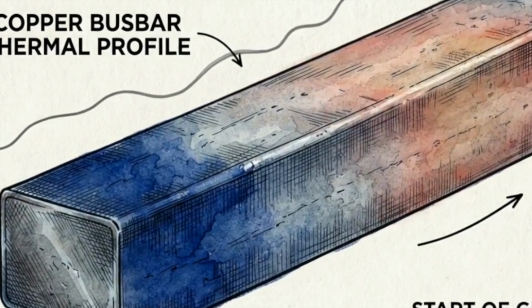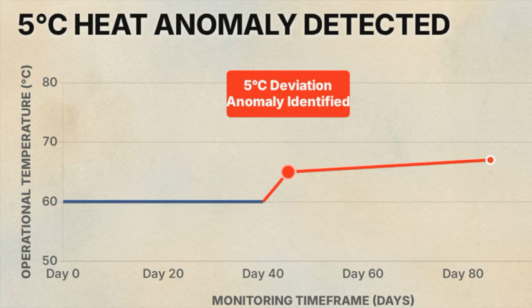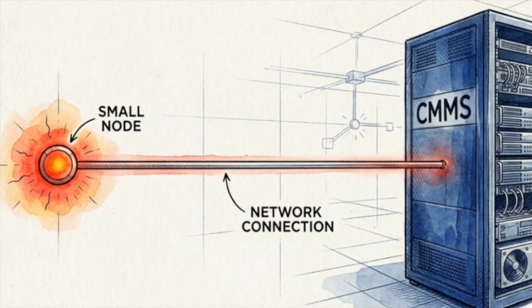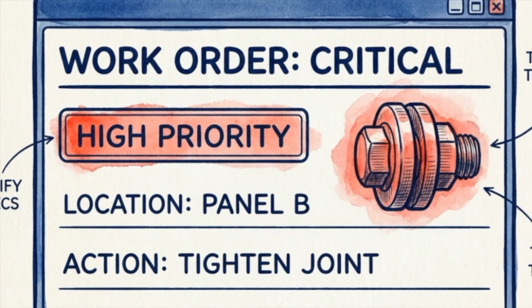The software logic is trained to detect a 5-degree deviation from the baseline. It identifies the heat anomaly the moment it begins, providing a warning long before there is any physical smoke. This data flows into a computerized maintenance management system. The AI bypasses human analysis to directly generate a prioritized work order based on the severity of the heat.